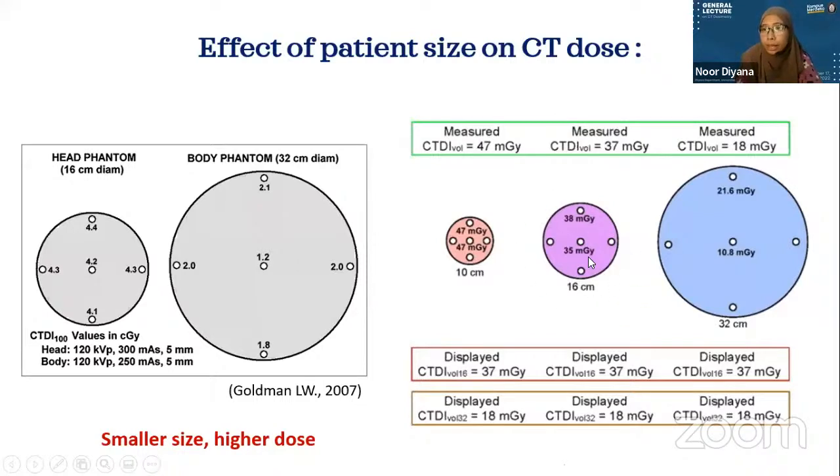So by using the SSDE correction, we determine the correct size of the patient, and we multiply by the correction factor for the correct effective diameter of the patient.